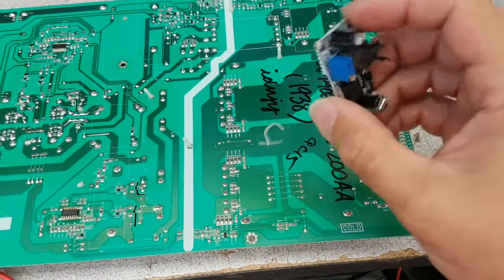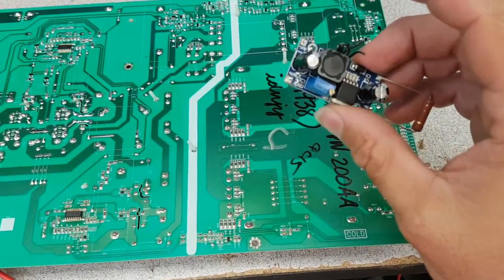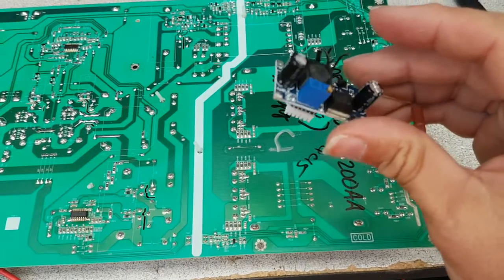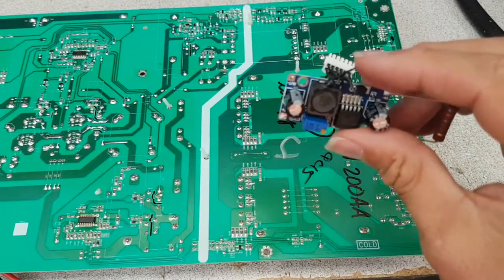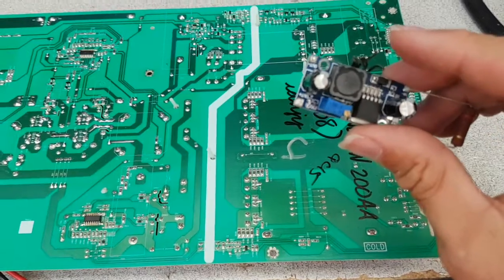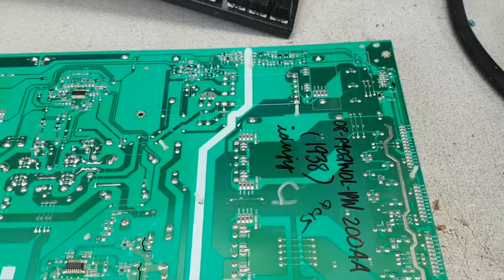Number one, remember the voltage you activate it with. I wouldn't be surprised if passing 24 directly works, but it needs more than 5 volts to jump out - it needs about 10. Number two, load the standby 24 in order for it to hold.